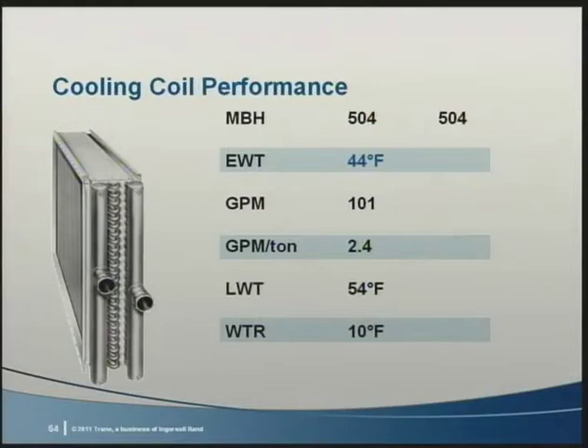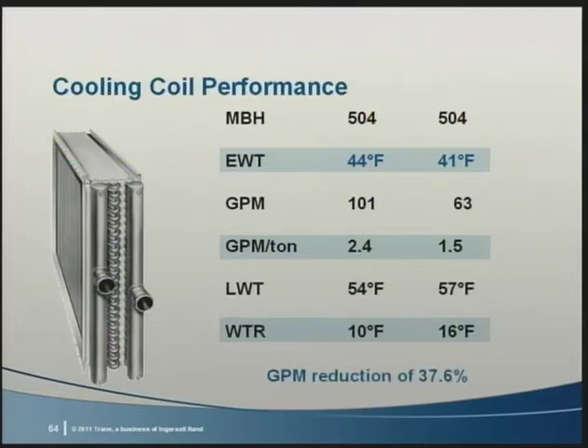Since the airflow and the entering and leaving air conditions are the same, this coil must still produce the same MBH, 504. But what if we send the coil colder, 41-degree water? In response, the coil valve modulates to allow less of that cold water, reducing the flow rate to 63 GPM. Note that the reduction to 1.5 GPM per ton is in line with the ASHRAE Green Guide recommendations. This results in an increase in leaving water temperature to 57 degrees, giving a 16-degree water temperature rise.